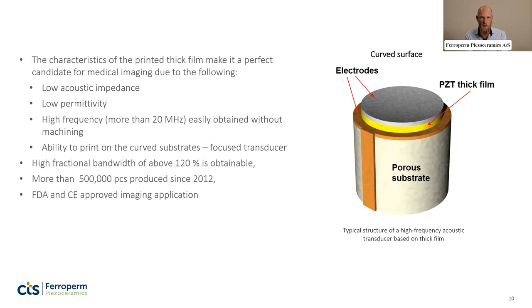So you can imagine a curved thick film with a certain thickness, and then by exciting the thickness mode of that thick film, we're able to emit an ultrasound pulse at a very high frequency corresponding to that thickness. So that's how we get up to the tens of megahertz range. And the properties of the thick film and the substrate are such that you get a very wide bandwidth transducer. You get a very damped pulse at very high frequency, which is really good for imaging. This lends itself to very high volume manufacturing of high frequency transducers, and this is one of the successes that we had in the past.